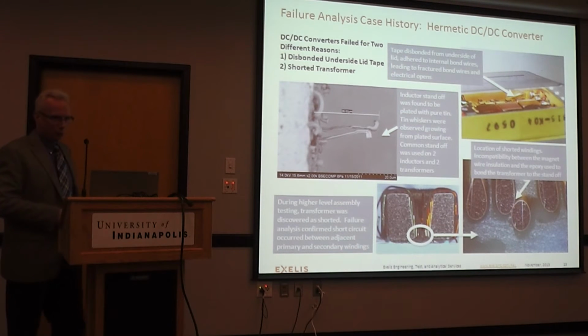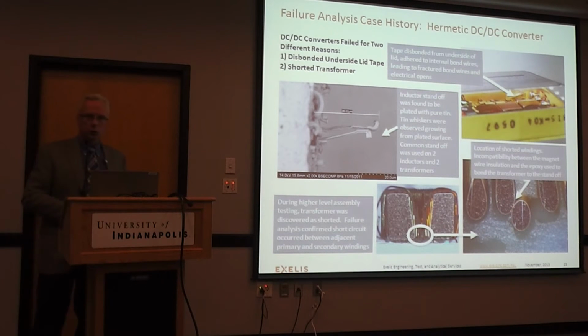It took about a week to determine, because this involved research on a number of materials. There is a potting material used to bond the transformer to the standoff. That potting material was incompatible with the magnet wire insulation, so it essentially softened, dissolved, and affected the physical properties of that wire insulation. Unbeknownst to the manufacturer of this module, they had used an incompatible material.